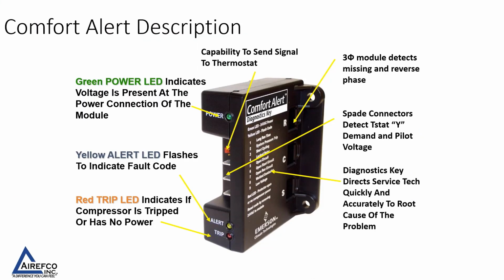On the Comfort Alert device, the green power LED indicates that voltage is present at the power connection of the module. The yellow alert LED flashes to indicate a fault code, and the red trip LED indicates if the compressor is tripped or has no power. It also has the capability to send a signal to the thermostat that will alert the end user of a problem. The three-phase module detects missing and reverse phase, and there are spade connectors to detect thermostat Y demand and pilot voltage. And right on the diagnostic device, there is a diagnostic key that directs the service tech quickly and accurately to root causes of the problem.